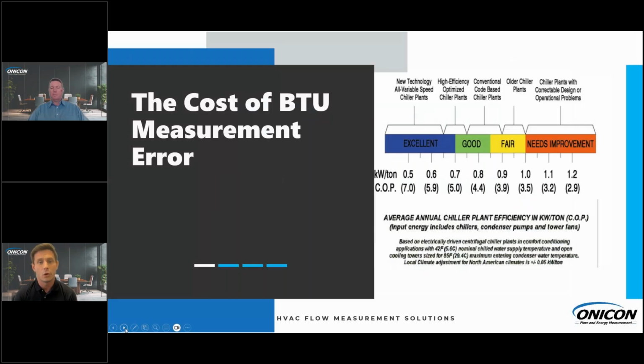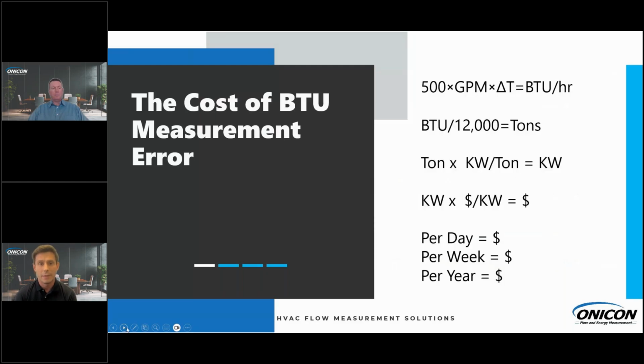So let's look at the cost of BTU measurement error. Chillers have a wide range of efficiency. Let's just assume this is a pretty efficient chiller at 0.75 kilowatts per ton. And you look at the math, the equation to calculate BTUs: you have that specific heat constant of 500, the flow in GPM, and the delta T. As you can see, that equation is proportional across the board. So you can see the importance of the error being minimal for an accurate calculation.